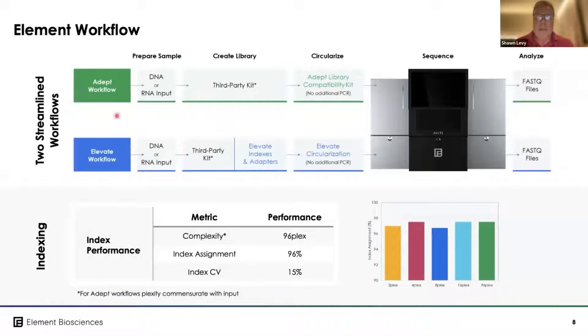That means we have two streamlined workflows to put samples onto the instrument. The first is the Adept workflow, which allows any standard Illumina library from any vendor, as long as the P5 and P7 sequences are intact and it's a double-stranded DNA library. That kit circularizes the library to make it compatible with the AVITI sequencer — no additional PCR or amplification — so you can go directly from an existing library prep onto the sequencer.